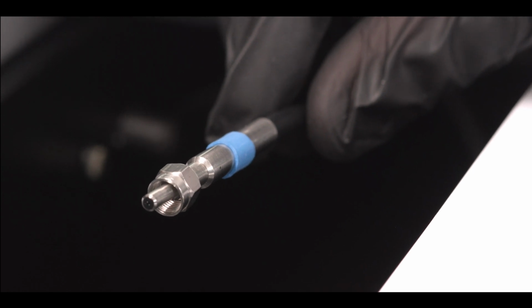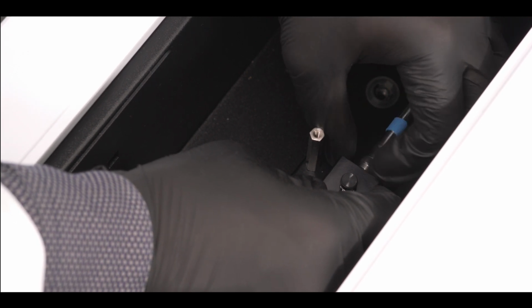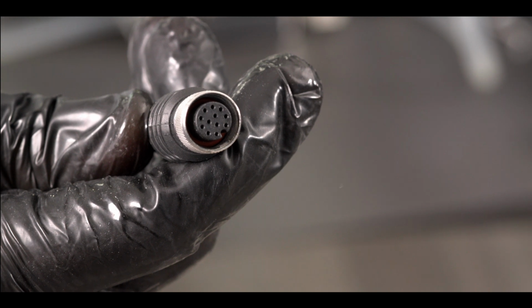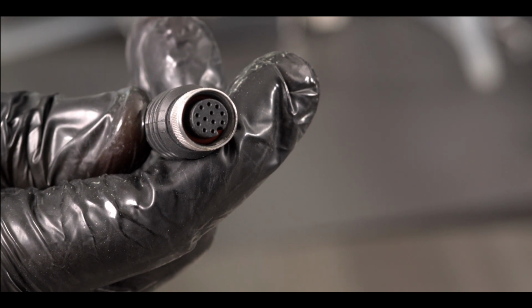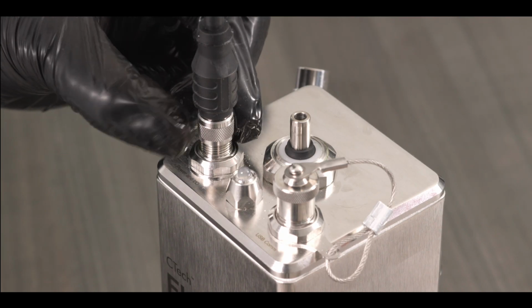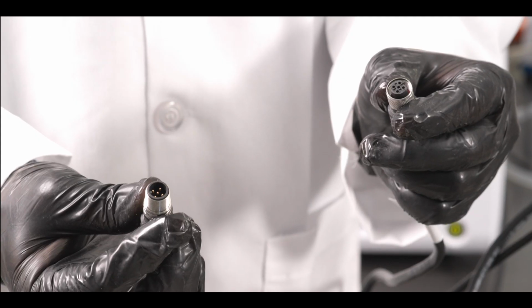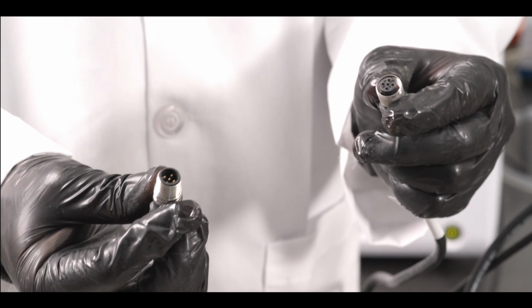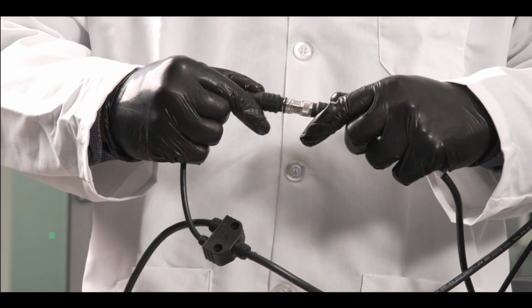Connect the SMA end of the delivery fiber to the threaded splice bushing at the back of the fiber optic coupler. Use the hex nut to securely tighten the connection. Connect the FlowVPX power and input-output I/O splitter cable to the top of the FlowVPX head. Next, connect the FlowVPX power supply to the power and I/O splitter cable.